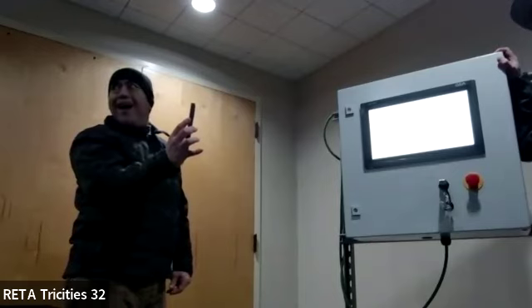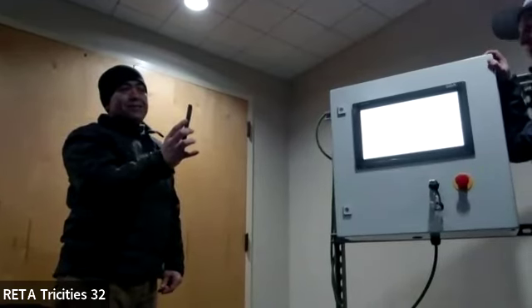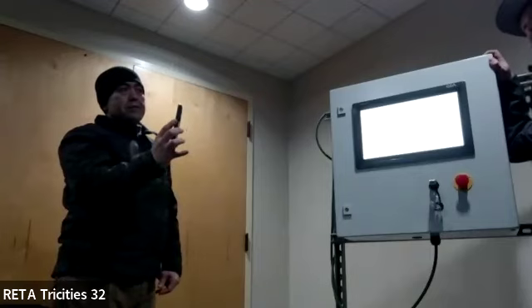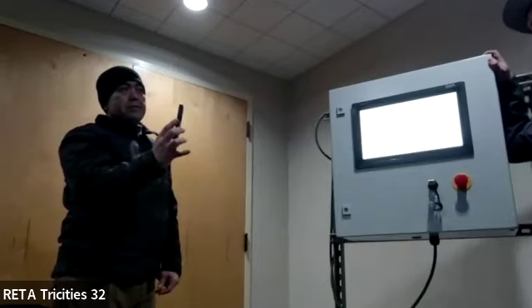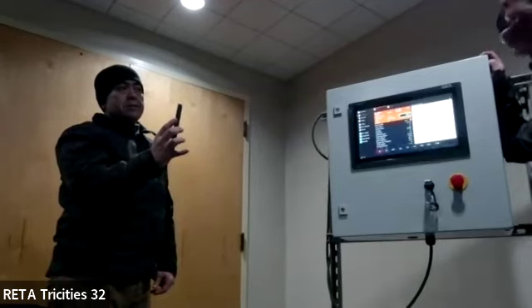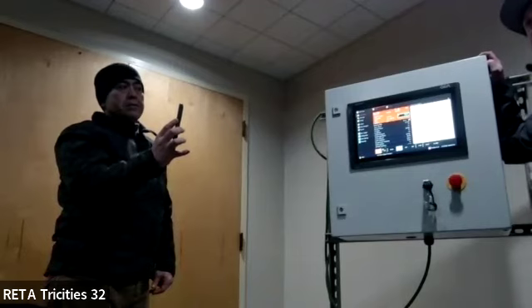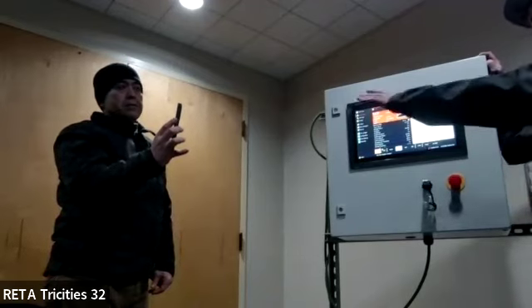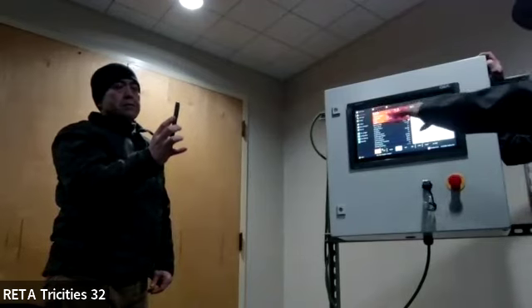So Cody, if I came and I see my machine is hunting, what would you look for? Hunting on the slide valve. Yep. Look for calibration. And I would look at your dead band. That's where I kind of start. The pulse of the solenoids. Yep, default is set at 4 seconds. You'd look at that too, and then you can make adjustments to needle valves as needed. Like, let's say a 4-second pulse and it's loading real fast. That's where you're going to want to adjust your needle valves, maybe bump it down to a 1 or 2 second pulse.